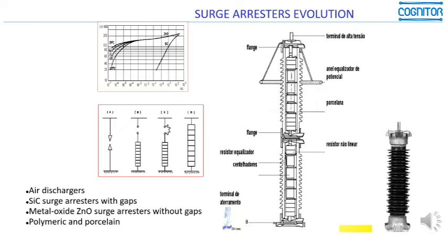That's the reason why polymeric surge arresters are now practically replacing all use of porcelain. They are much lighter, easier to install, and do not have this problem of explosions.